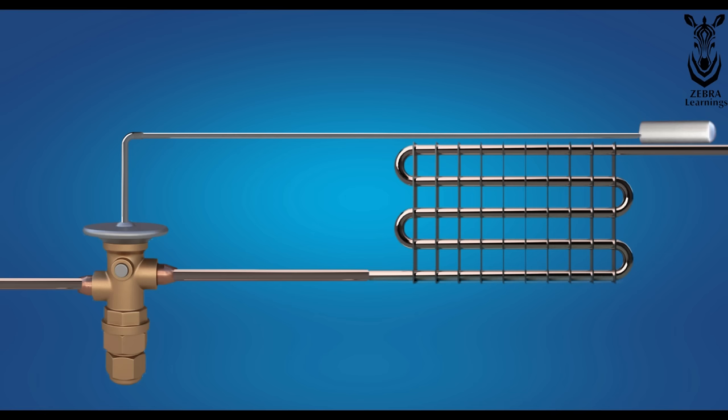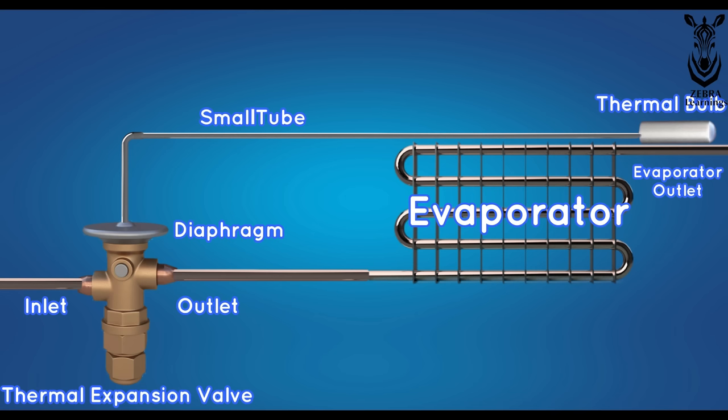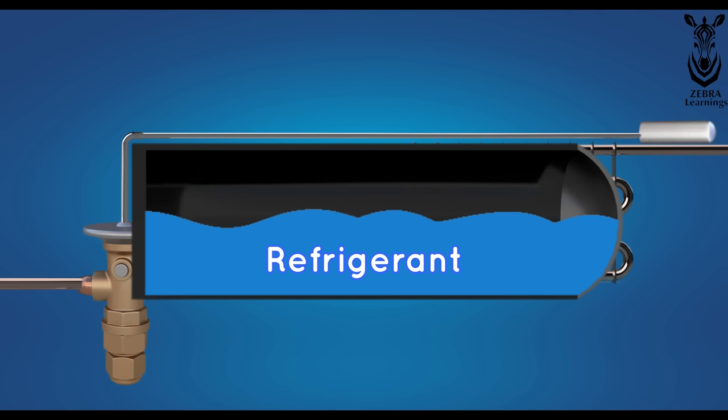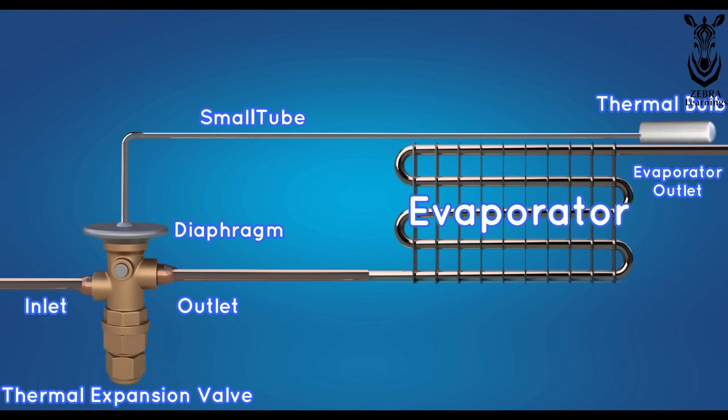The thermal bulb is connected to the outlet of the evaporator, like this. There is refrigerant inside this thermal bulb. The refrigerant used in the thermal bulb is the same refrigerant used in the AC unit. For example, if R410A refrigerant is used in the AC unit, the same refrigerant is used in the thermal bulb.